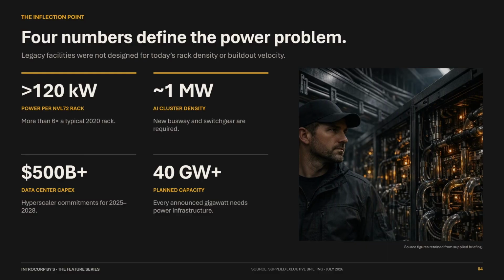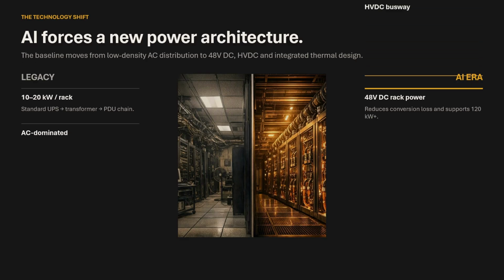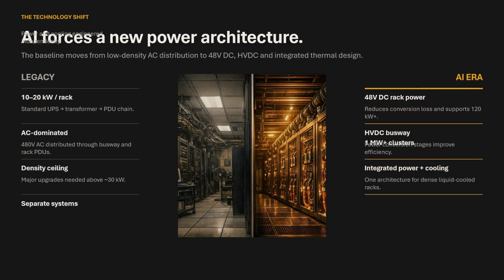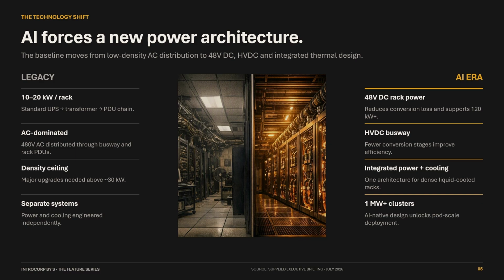Every rack, cluster, and announced gigawatt depends on physical power infrastructure. That is where deployment schedules can accelerate or stall. The response is not simply to install more of the old equipment; the architecture itself is changing. Traditional server rooms were designed around roughly 10 to 20 kilowatts per rack, AC-heavy distribution, and separate power and cooling systems. The AI era baseline moves toward 48-volt DC rack power, high-voltage DC busway, and integrated thermal design. These changes reduce conversion losses and support much denser clusters. In other words, AI is forcing power and cooling to become one coordinated system rather than 2 independent facility functions.